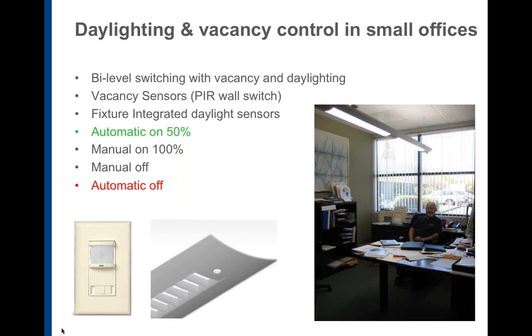For small offices, we've done several studies over the past few years that show excellent results for automatic on when the occupant enters the space, and then if they need more light, they have somewhere to go, so they go up to 100 at that time. Automatic off after the space is vacant for up to 30 minutes, and we found that that even is not necessary. 15 would be fine, and a tremendous amount of savings can be achieved through these measures.